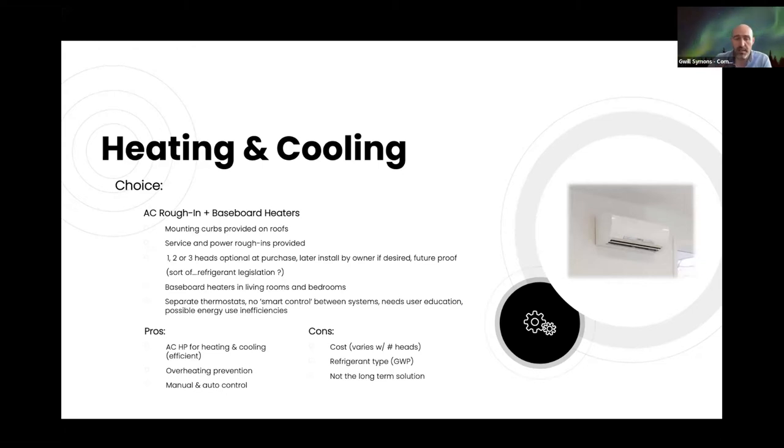The cooling option we settled on was AC rough-in with baseboard heaters. We're putting curbs on the roofs and roughing in the power and services at construction. Purchasers will have the opportunity to put in one, two, or three heads in bedrooms and living spaces at time of purchase, or install them later. Baseboard heaters cover bedrooms and living rooms, though there's no smart control between the two systems if AC isn't installed, so user education will be important to avoid simultaneously heating and cooling.